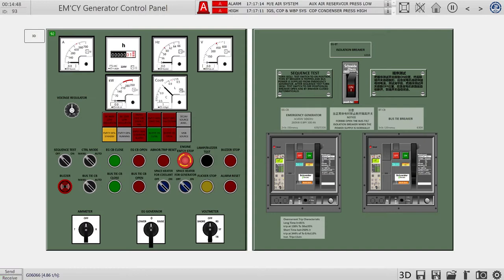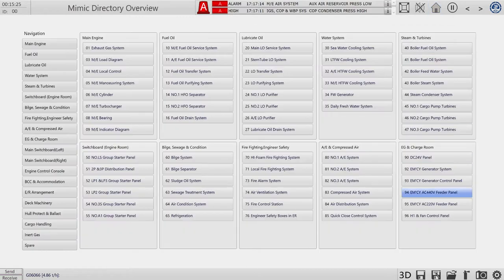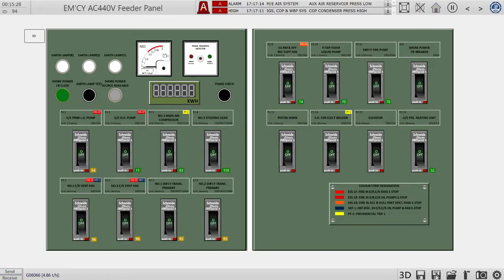I will switch on the isolation breaker and connect our bus tie — it's closed now, supplying the emergency panel. We can also switch on the heaters and set them to auto control mode. Now we will go to our 440-volt panel and switch on the heating and the elevator, which are really essential.